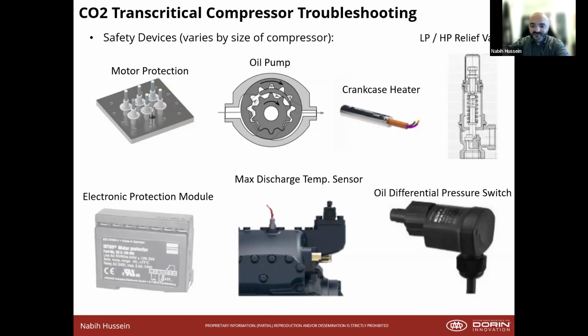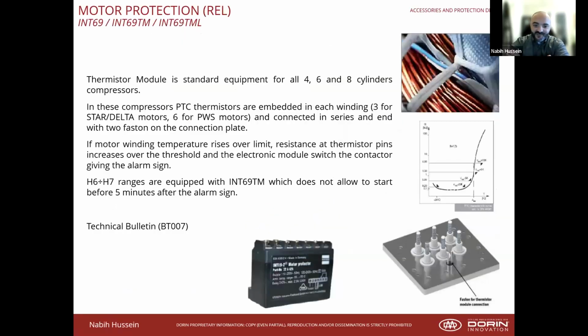We have a crankcase heater, which is used to keep the oil temperature above the point where liquid CO2 would be inside that crankcase, inside the oil sump. And that's so on startup, you don't have liquid CO2 flashing off inside of your metal surfaces. There's the low pressure, high pressure relief valves. The low pressure relief is set at 1,349 psi, and the high pressure relief is set at 2,030 psi. Those are to protect the actual compressor itself from overpressurizing. All of these safety devices only work if they are electronically connected in series with each other. And I bring it up only because if you bypass any of these safety features, they no longer protect the compressor.